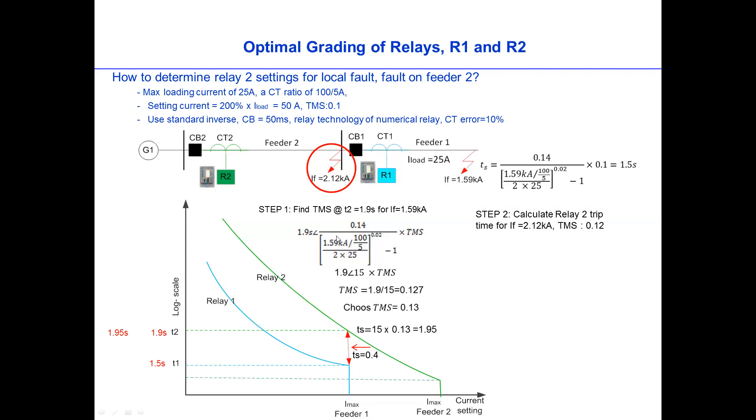And then the next step is, because this is for fault at the remote end. Now, the step is to calculate Relay 2 trip time for local fault. So now we come back to the question here. On this local fault. Since we have the TMS value 0.12, or we can choose 0.13. Then we can calculate here. Now we just need to change the fault current here. Instead of 1.59, we just change it to 2.12. And then the rest is the same.